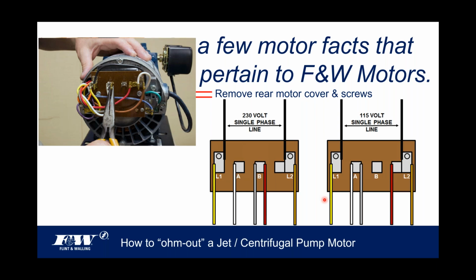And yet, I've had some people complain a little bit that they feel like this is a little too cumbersome. There are other manufacturers out there with dials and slide switches, and I've talked to contractors about those. And I'm going to tell you something, as far as my poll results, those things have not been flawless either. If the switch doesn't switch, now what? If the dial doesn't actually make the voltage change, now what do you do? Here, with a pair of needle nose pliers, I can probably perform this operation in less than a minute, just taking that back cover off and moving those two wires.